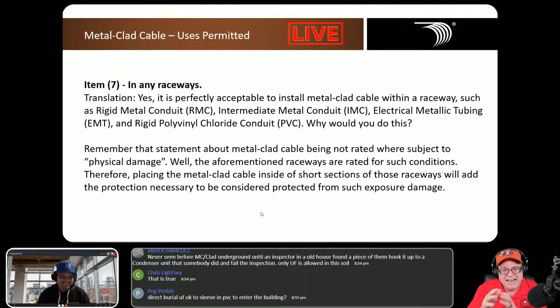So, again, all raceways are designed to drain. You have to arrange to drain so that it allows moisture to get out of those raceways. And so, again, if it's for physical damage, for example, yes. If I want to sleeve it in a raceway, just to sleeve it in a raceway, absolutely, you're still allowed to do that. You're just going to have to be careful about raceway fill calculation. Can I sleeve NM-B in a raceway? People wonder that all the time. Absolutely, just not outside in a wet location. Perfectly fine. So again, perfectly okay to put it in a raceway, and you get that permission from item 7 right there.